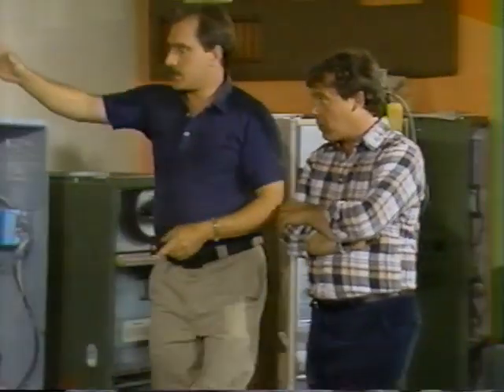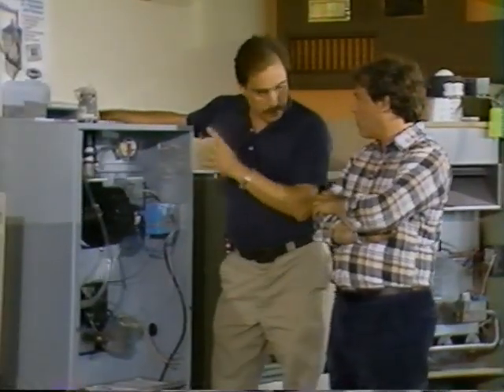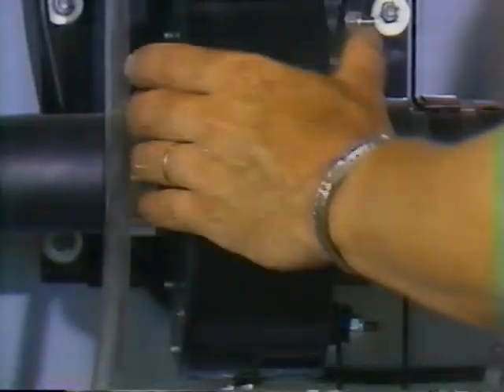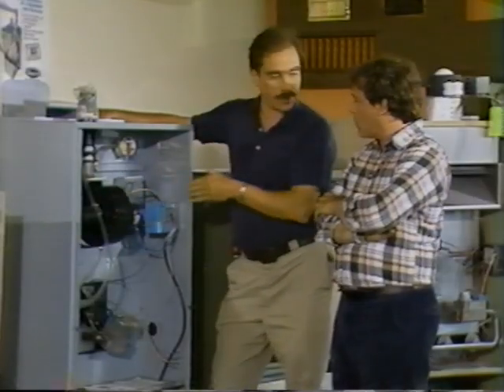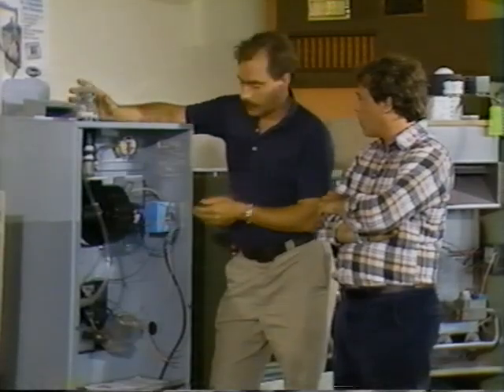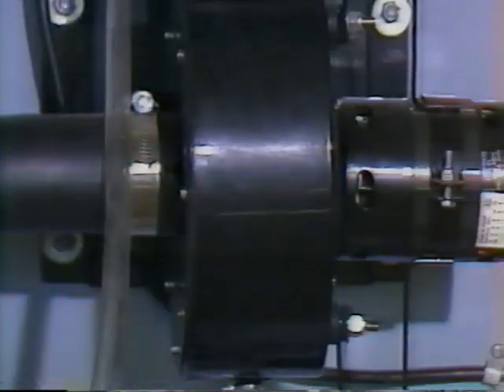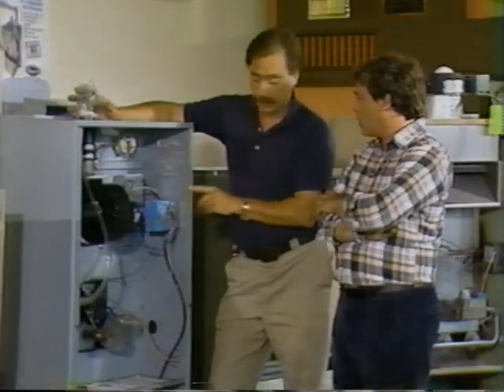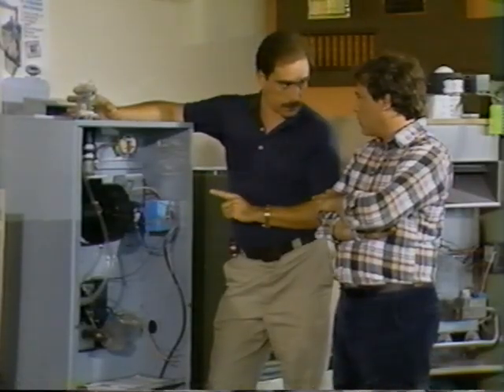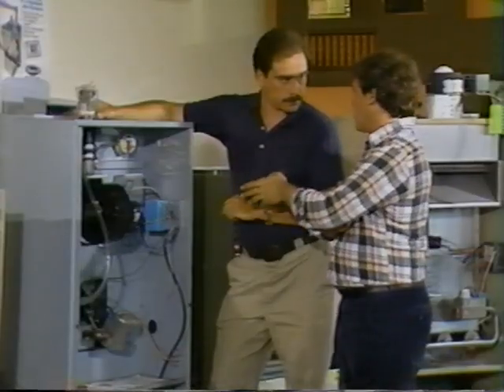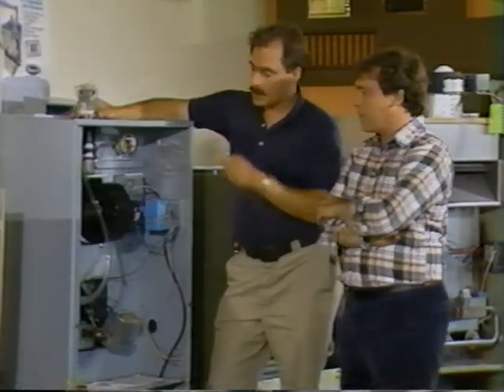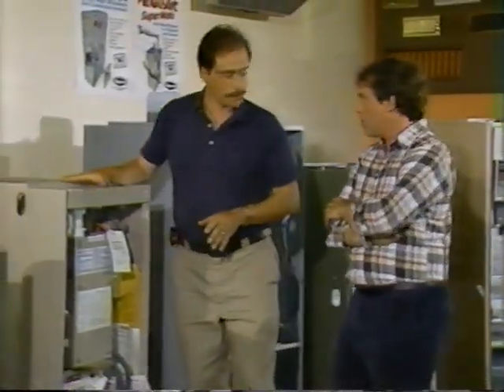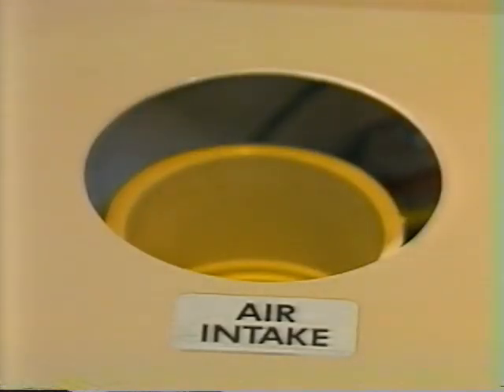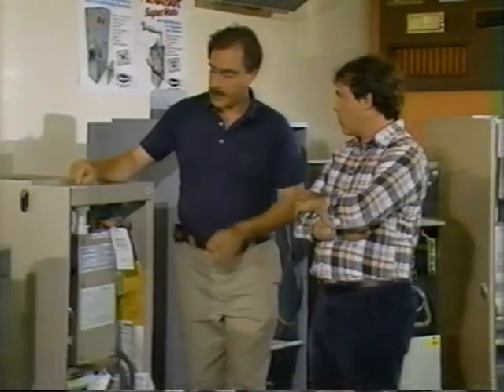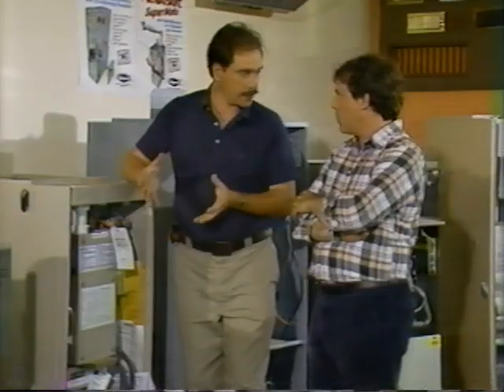Next unit up is, again, a large heat exchange area, again a very efficient induced draft unit, but in this case the heat exchanger has become so large that the flue gases are cooled to the point where we get a condensate out of them. This is an extremely efficient furnace and a very, very good choice, but again you must bring exterior air to the unit. So the term condensing furnace means one with so much heat exchanger that it cools it. Exactly. That far. This one is totally sealed combustion. Ideal for the job that we're trying to do because it is actually bringing its own air in from outside and again exhausting the products of combustion through a pipe. Totally outside the air volume in the house itself.